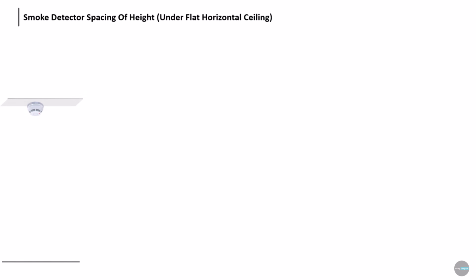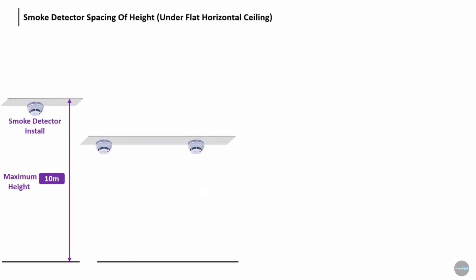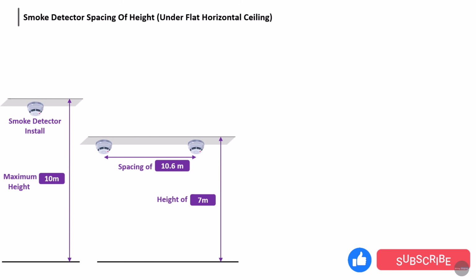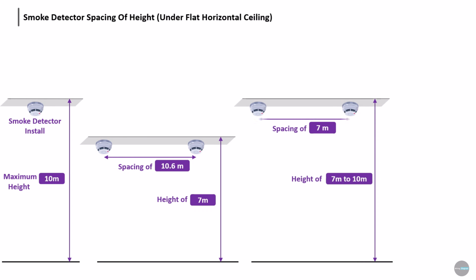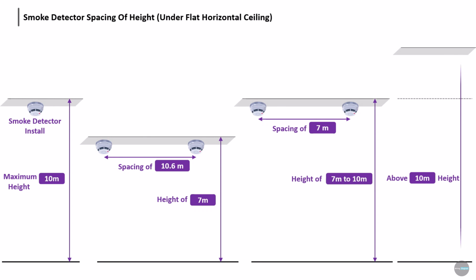According to standard, the maximum height for mounting a smoke detector is 10 meters. If the ceiling height is up to 7 meters, the spacing between detectors should be 10.6 meters. If the ceiling height is between 7 and 10 meters, the spacing should be 7 meters. And if the ceiling height is above 10 meters, then smoke detectors are not suitable. In that case, we use beam detectors or aspirating smoke detection systems.